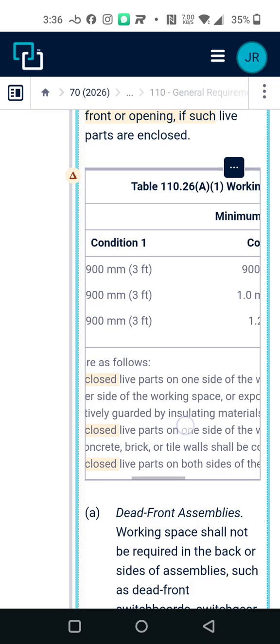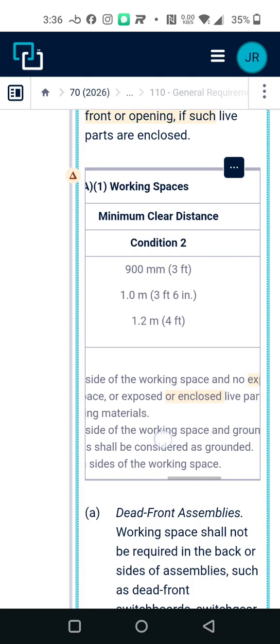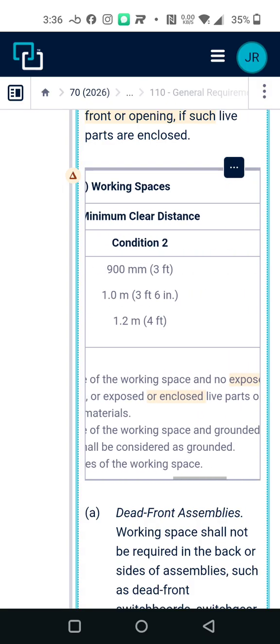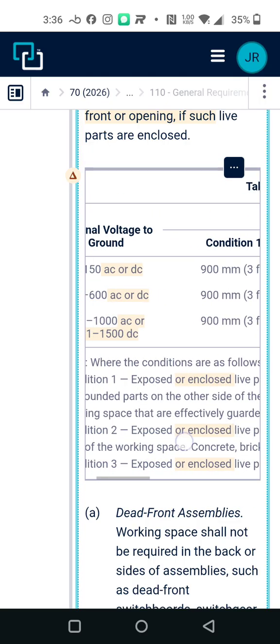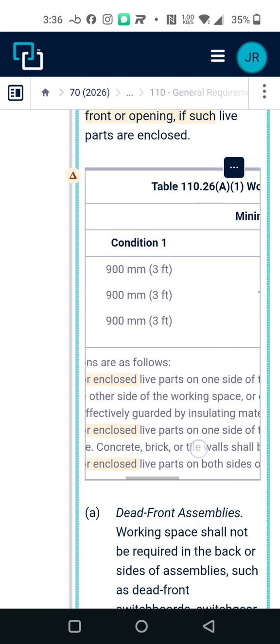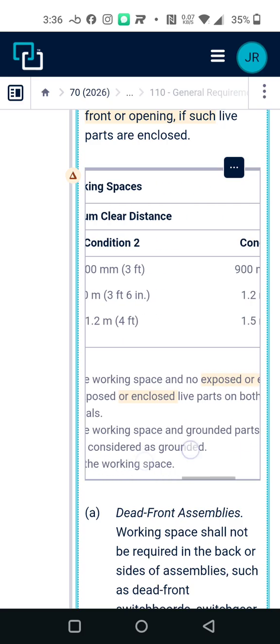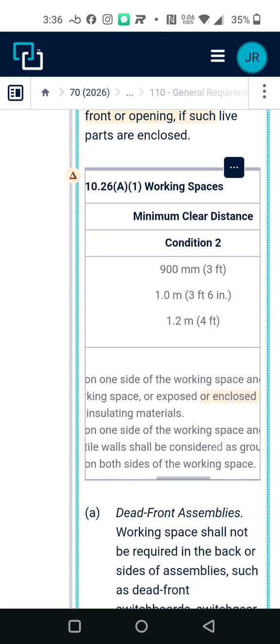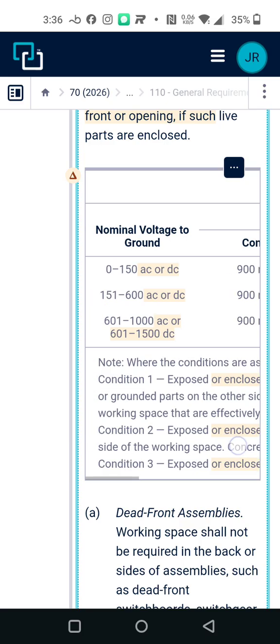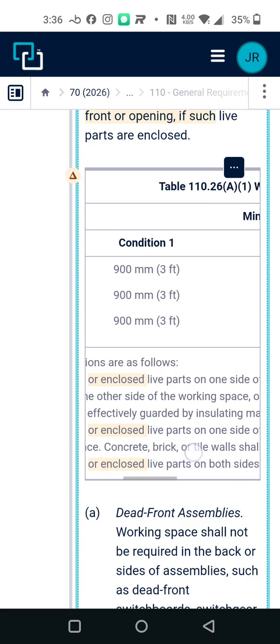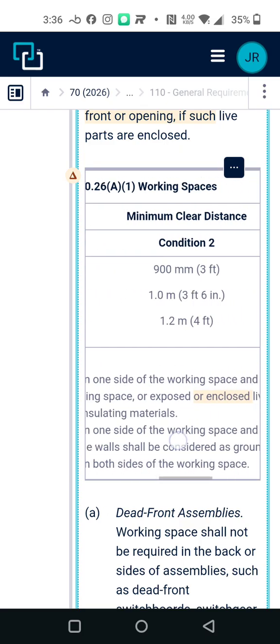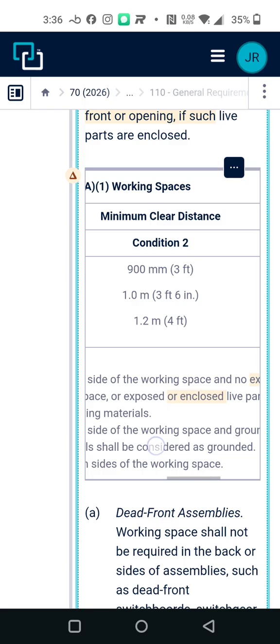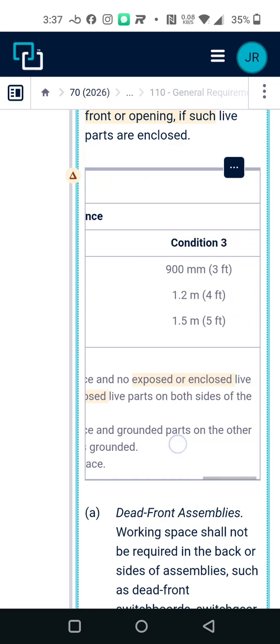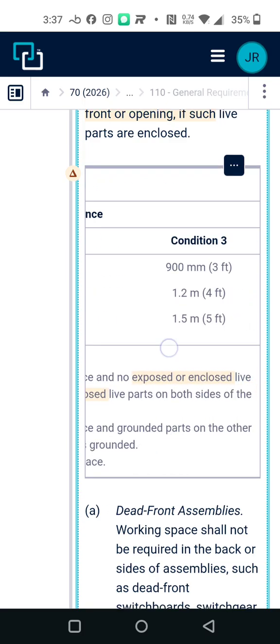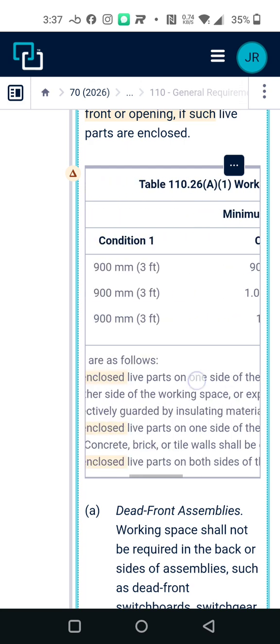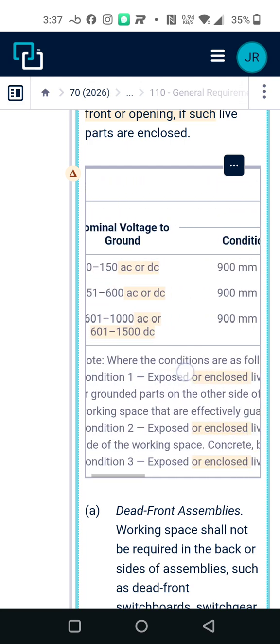Exposed or enclosed live parts on one side of the working space, and no exposed or enclosed live or grounded parts on the other side of the working space, or exposed or enclosed live parts on both sides of the working space that are effectively guarded by insulating materials. See, condition 2 is different. Condition 3 is different. And you see different conditions.